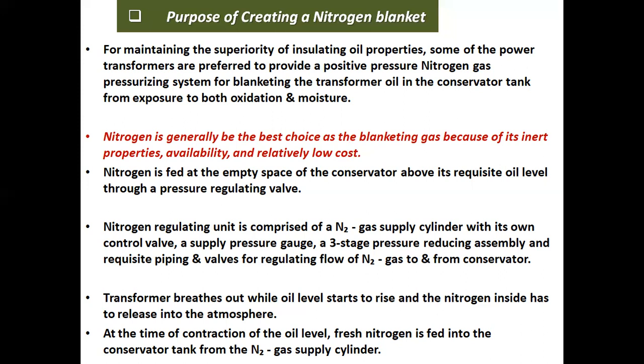The nitrogen regulating unit is comprised of nitrogen gas supply cylinders with their own control valve, a supply pressure gauge, a three-stage pressure reducing assembly, and requisite piping and valves for regulating the flow of nitrogen gas to and from the conservator. As the transformer breathes out and the oil level starts to rise, the nitrogen inside has to be released into the atmosphere. At the time of contraction of the oil level, fresh nitrogen is fed into the conservator tank from the nitrogen gas supply cylinder.